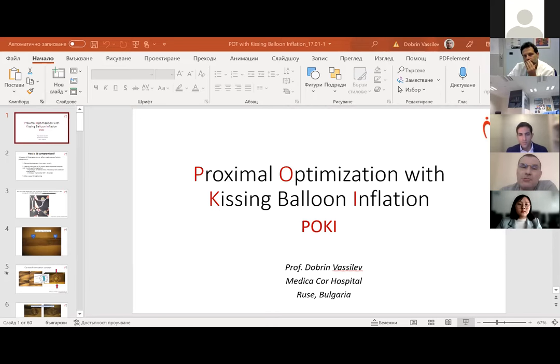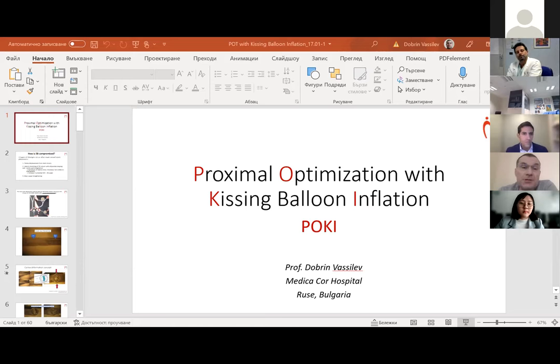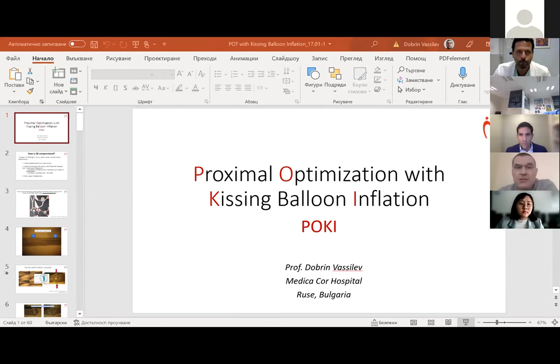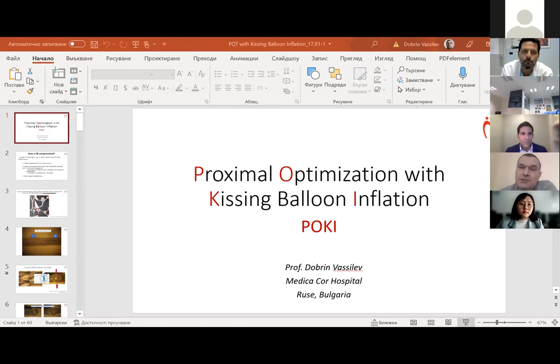We made a lot of bench testing on the elastic models concentrating on the deformation of the wall. This is the model we used — an elastic model where we implanted a lot of stents just to check not only the stent deformations but also the model deformations, which are similar to coronary vessels. We observed that there is a carina shifting but also this type of elliptical stretch on the lateral walls in the plane which is perpendicular to the plane of the main vessel and side branch.